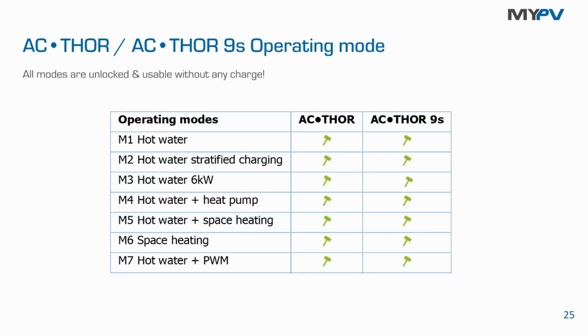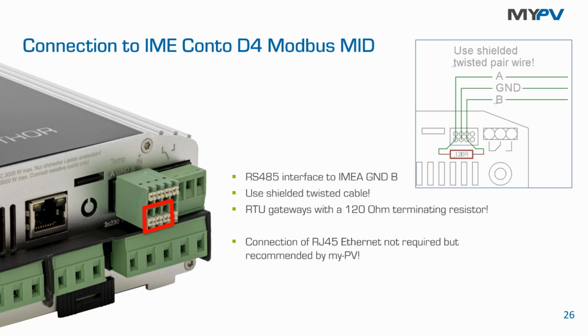Both variants of the AC THOR come with 7 predefined operation modes. These are more or less standard modes. The most common one by far is mode 1, the hot water mode. And this means that there is an immersion heater connected to the AC THOR. This immersion heater can either be assembled in a hot water boiler or in a storage tank. It does not matter. And here we also see how you connect the AC THOR to the IME meter. And once again, we always recommend using Ethernet as well to have remote access to our device.